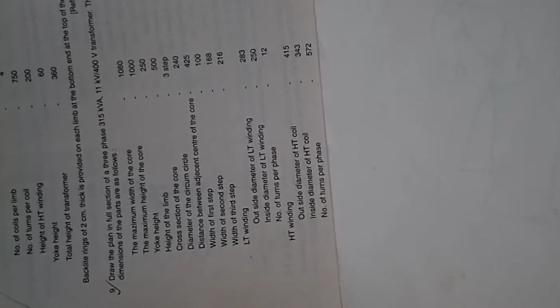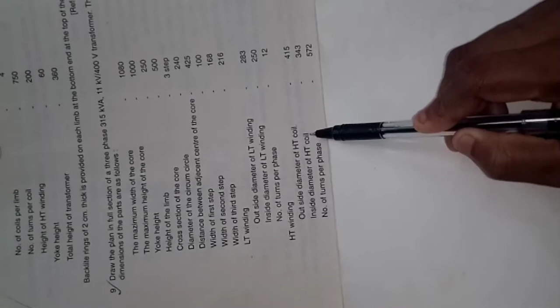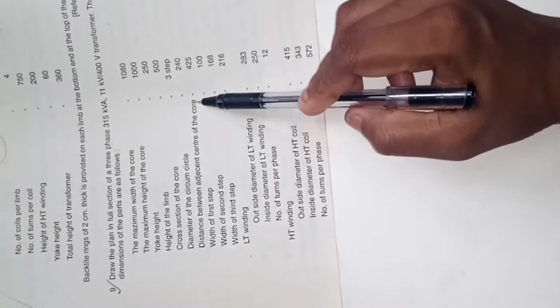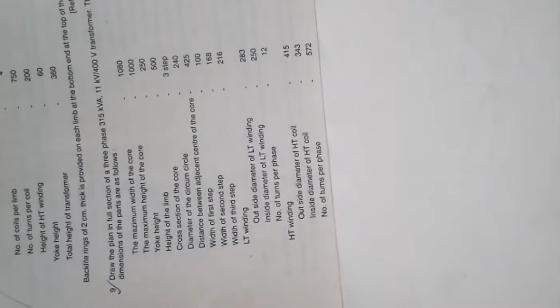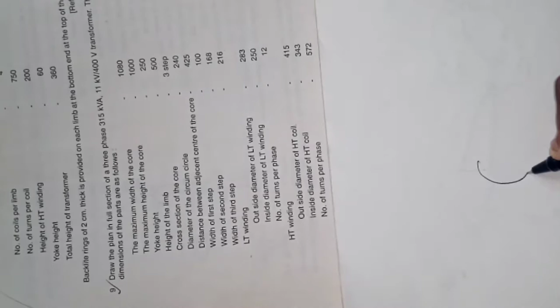So this is the question. From the data itself we can start. It is given: outside diameter of the LT winding, inside diameter of the LT winding, outside diameter of the HT coil, inside diameter of the HT coil, and distance between adjacent centers of the core. This is the first step. Since ours is a three-phase transformer, there will definitely be three circles.